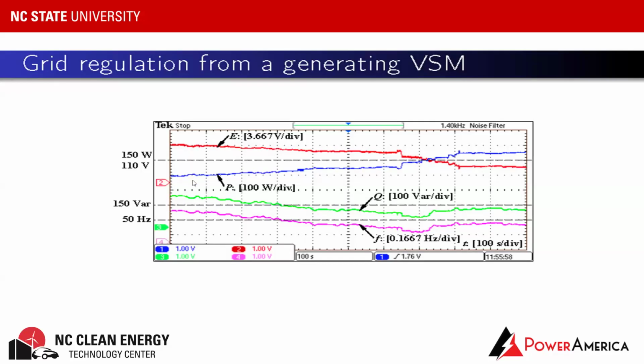You see that the power sent to the grid is more or less symmetric with the voltage. When the voltage is increasing, the real power is increasing. That means the virtual synchronous machine senses that the grid needs more power and then increases the output to support the grid. And for the reactive power, it changed in the same way as the frequency. So when the virtual synchronous machine senses that the grid needs more reactive power, it sends more reactive power to support the grid. In this way, the virtual synchronous machine is able to support the grid frequency and the grid voltage stability. Note that all of this is done autonomously without any human intervention or communication. It is just connected and then operates autonomously to support the grid frequency and the voltage.